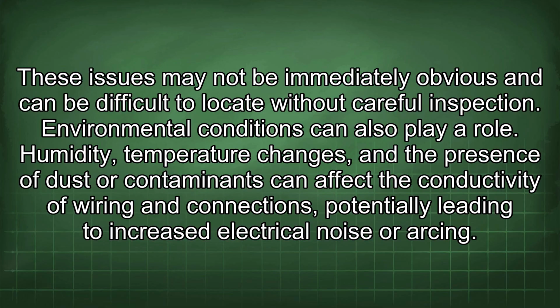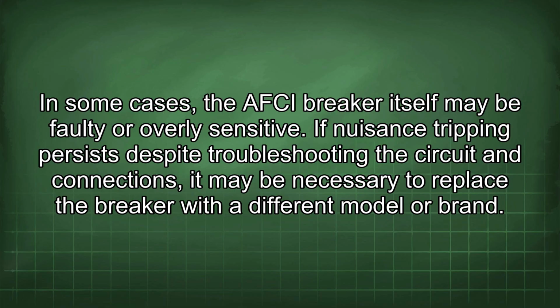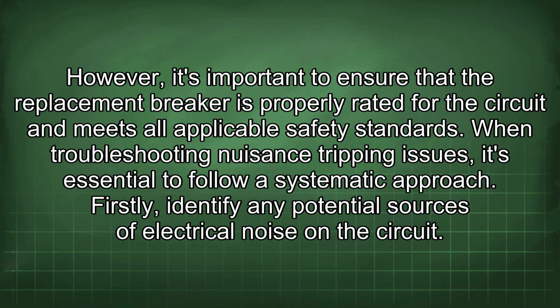Environmental conditions can also play a role. Humidity, temperature changes, and the presence of dust or contaminants can affect the conductivity of wiring and connections, potentially leading to increased electrical noise or arcing. In some cases, the AFCI breaker itself may be faulty or overly sensitive. If nuisance tripping persists despite troubleshooting the circuit and connections, it may be necessary to replace the breaker with a different model or brand. However, it's important to ensure that the replacement breaker is properly rated for the circuit and meets all applicable safety standards.